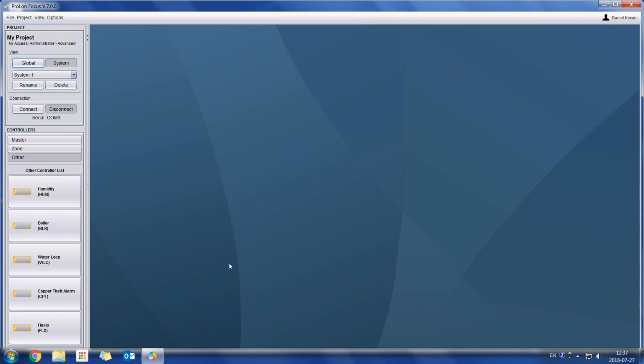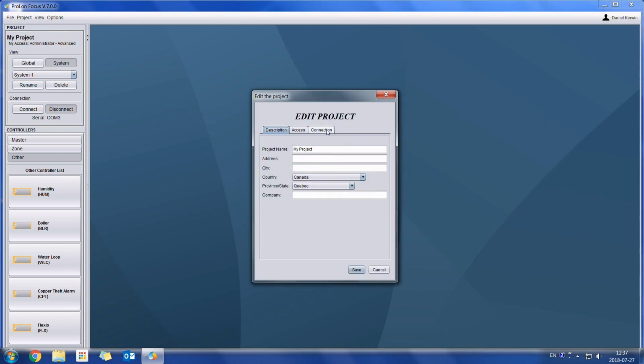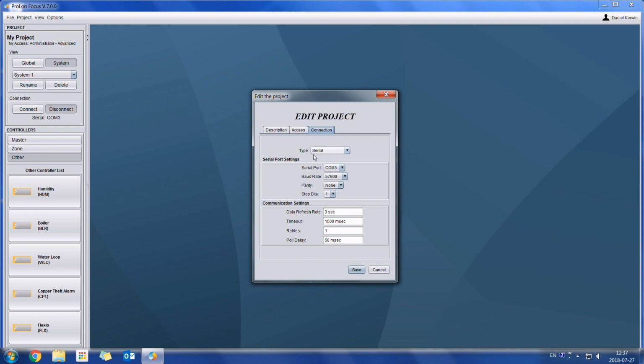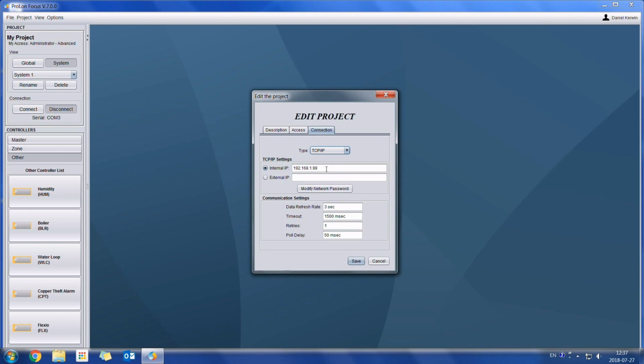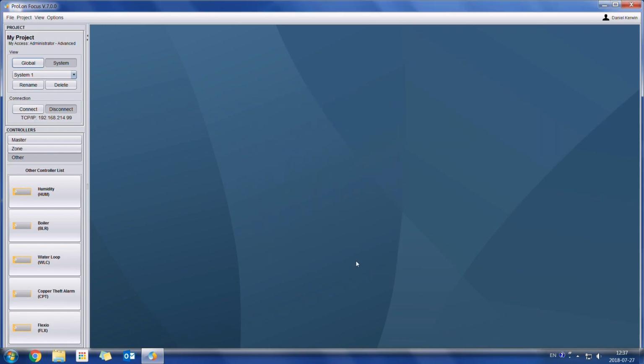In this case, I'm going to be connecting onto our office, and we're going to be doing it through an IP connection. So to set up the IP connection first, I'm going to go on Project, Edit, and I'm going to click on the connection tab right here. And I'm going to change the connection type from serial to TCP/IP. And in this case, I'm going through our internal network, so our internal IP. And the IP address of the network controller is 192.168.214.99. Click on Save.